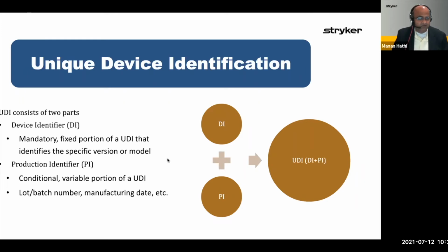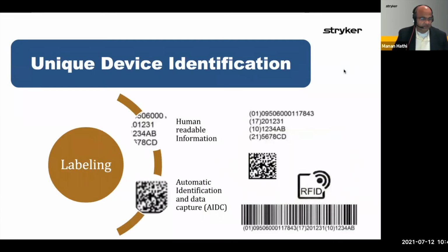The other part of the UDI is the variable portion. That's where it goes down to the specific unit. If you remember, the device identifier is the specific model or version of the device. The production identifier goes down to the specific unit, whether it be a serial number, in which case there can be no device with one DI and one serial number. There can be only one device for that, so there can be no other device that mimics that. Or it can go down to the lot or batch number or manufacturing date, what have you. So that's basically how you can go down to identifying a given device completely uniquely. In the next slide, we will go into a little bit more detail on what the production identifiers are.